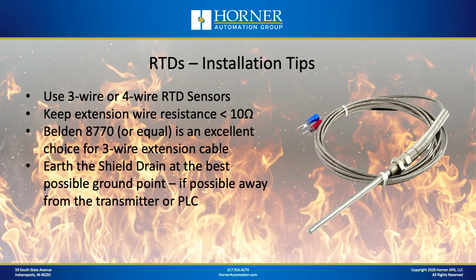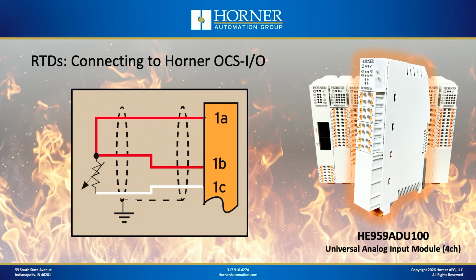Also, if you're going to be having a shielded extension cable, you're going to want to make sure that you earth that shield drain from the extension cable at the best possible ground. All else being equal, a ground away from the PLC might be best, but if the best ground happens to be close to the PLC, then ground it there instead. You never want to have a shielded cable where you don't deal with the shield drain. You're just causing that extension wire to act as an antenna in that case.